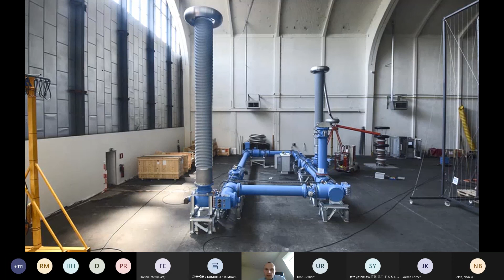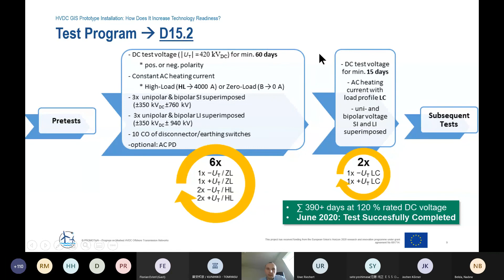Here, just a short recap. Nadu has told it in more detail. We had these 8 blocks with varying voltage and current load. All the blocks were terminated with the superimposed voltage. And in total, we can say we had more than 390 days of DC voltage of 120% rated DC voltage, so 420 kV all the time. And mid of last year, we completed the test successfully. And more details for the test program can, of course, also be found in the D15.2 deliverable document that's publicly available on the PROMOTioN website. So if anyone's interested in more details, I strongly encourage you to go to the website and look it up there.